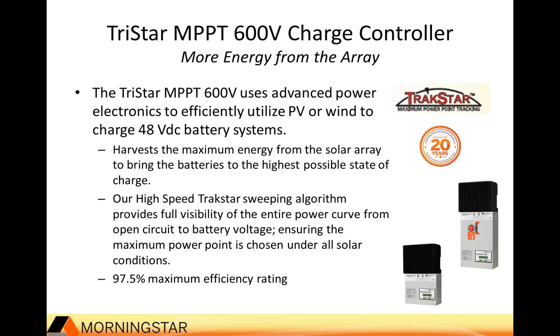As I said, it uses our Trakstar algorithm, so this is going to make sure to harvest the maximum energy from the solar array. And again, this is a technology that we've utilized in all of our product range to efficiently find the maximum power point. One thing we're also very proud of is that this product has a peak efficiency rating of 97.5%. So what we did with this design was we engineered it to operate extremely well at a specific point, and that would be a high voltage input, between 300 to 400 volts VMP, and output to a 48 volt battery. Because it was designed to do that specific voltage conversion very well, the efficiency is maximized. So we're looking at about 97.5%.